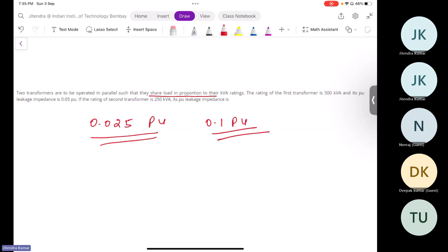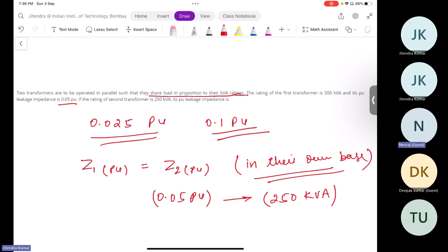So what you did here, who calculated 0.025 per unit, you transformed it to the same per unit, but it is mentioned that it should be on their own base. So whatever 0.05 per unit was for the first transformer, that will again be equal to 0.05 per unit, with 250 kVA. So its answer would be 0.05 per unit. Did you get it? Where did you make the mistake?